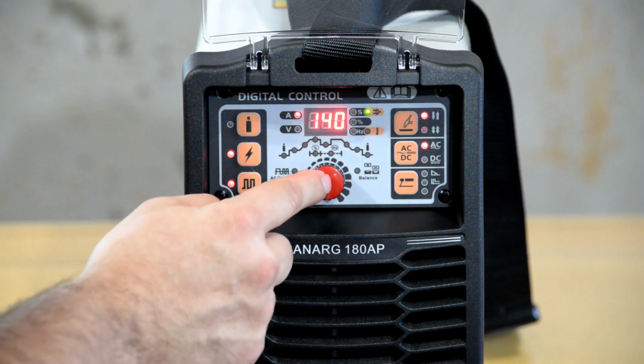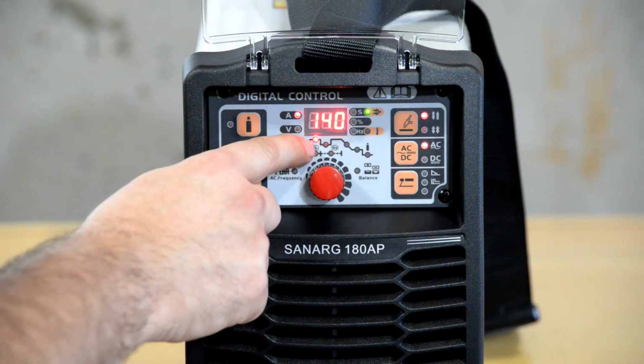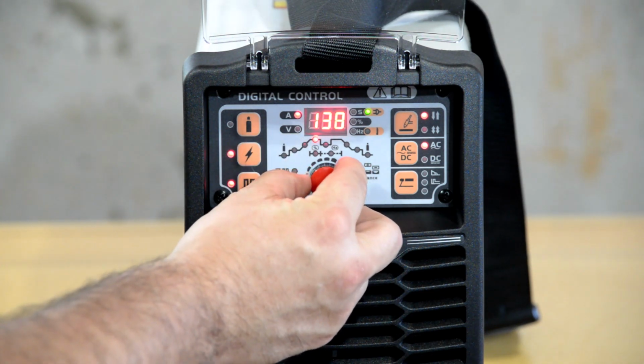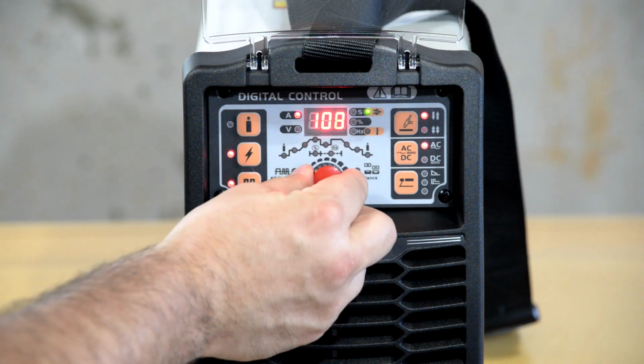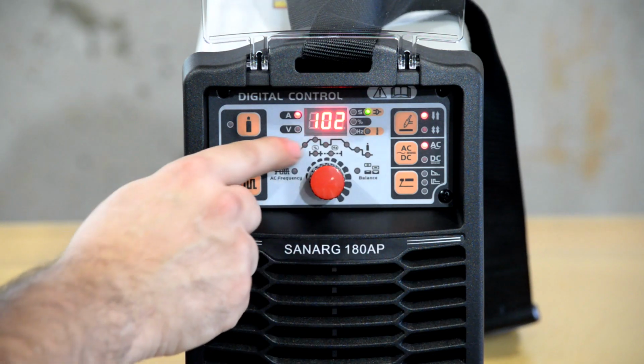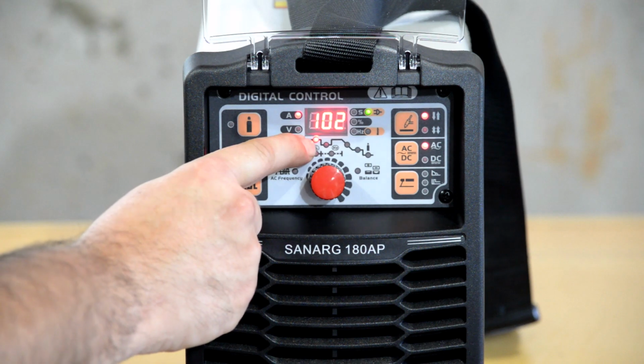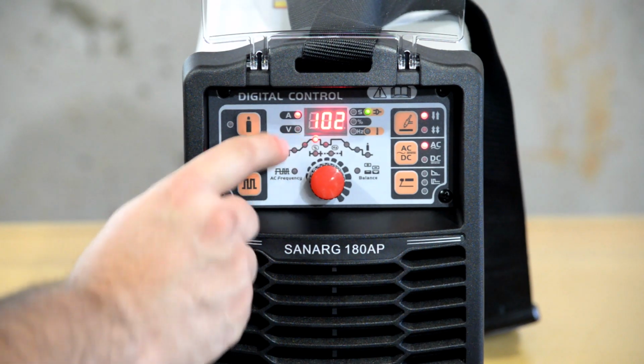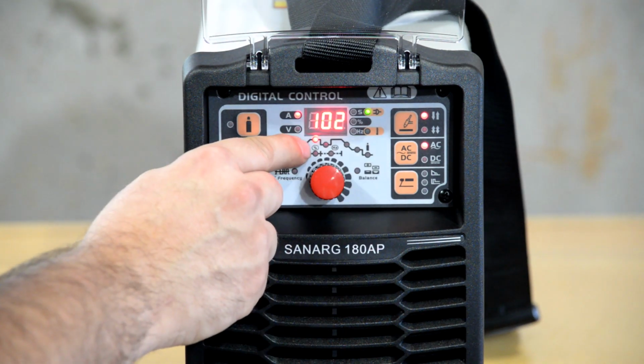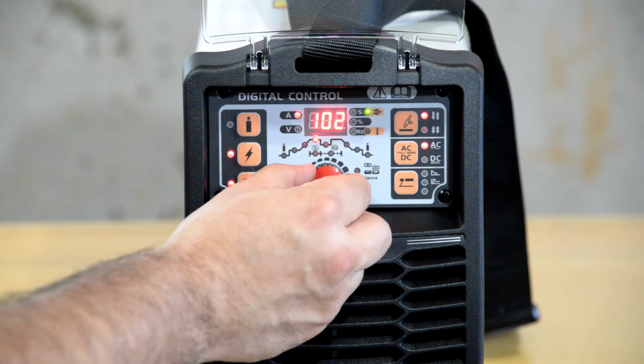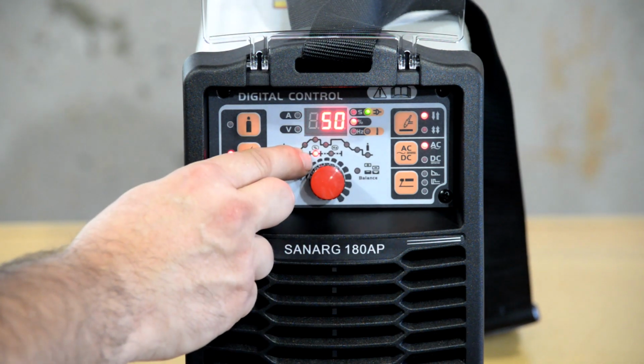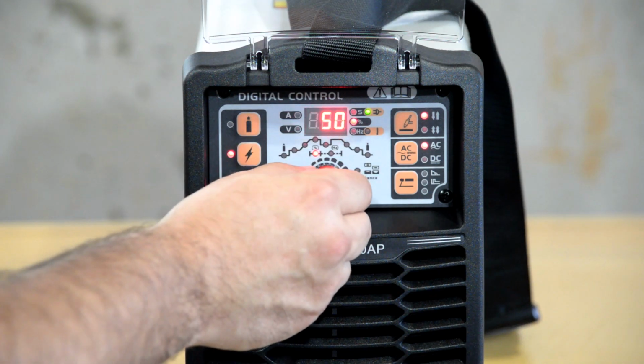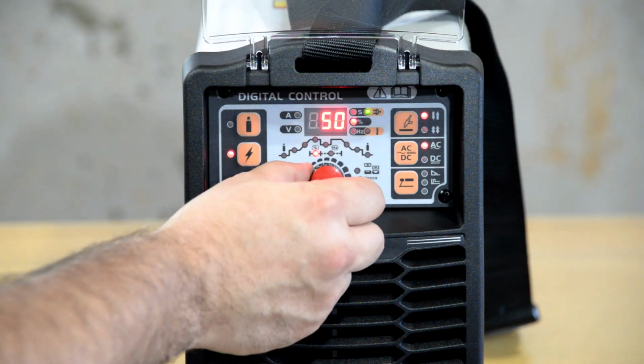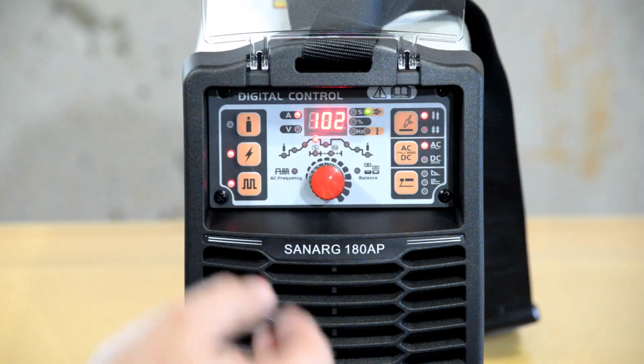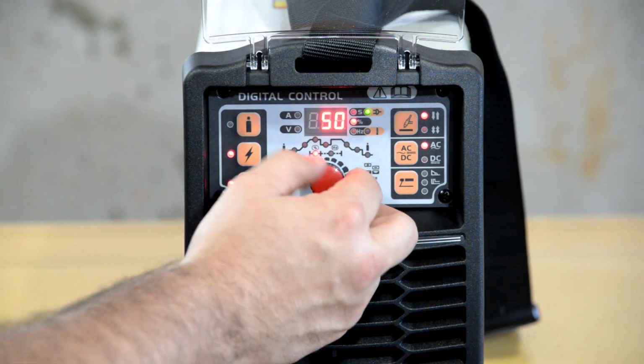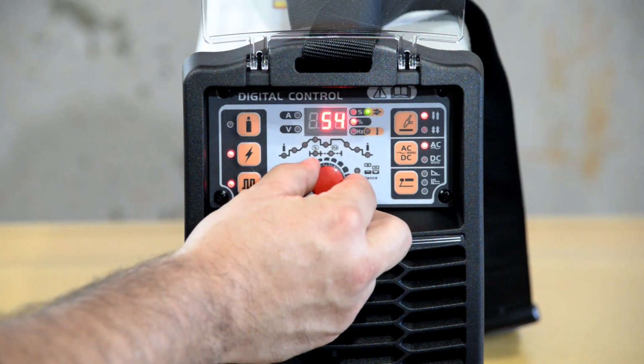To make an adjustment, we push the knob in till this LED starts flashing, and then we can make our adjustment. Since this is in this position, we're adjusting our peak current. When the light stops flashing, we can turn the knob, and that allows us to change the percentage, 50% between peak and background, and we can adjust that.